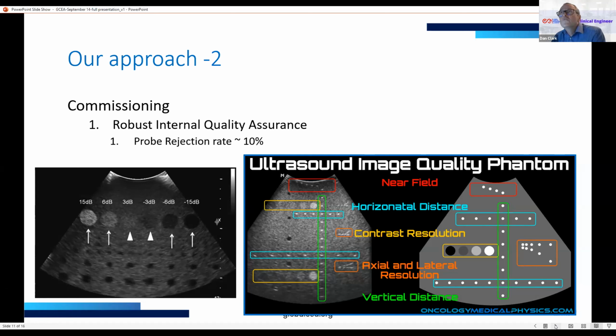However, a really key step when it comes to ultrasound devices, and what makes them different from, say, an infusion device or an electrosurgical unit, is that we also need to check the image quality and functionality. And in Nottingham, we do that by relying on our medical physics colleagues who do the image quality checks using phantoms.